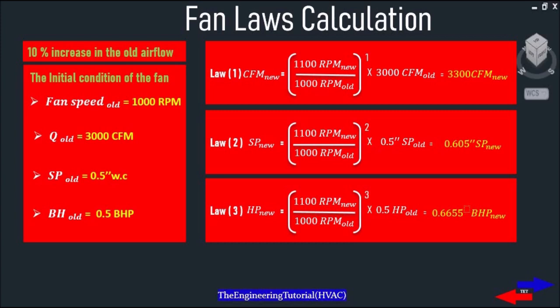First, CFM new equals 1100 RPM new divided by 1000 RPM old, multiplied by 3000 CFM old, which equals 3300 CFM new.